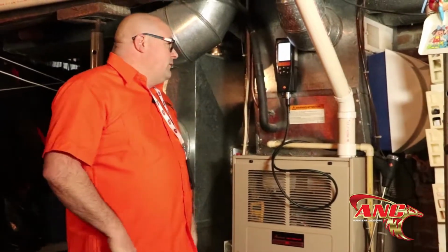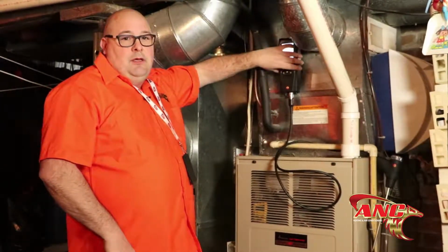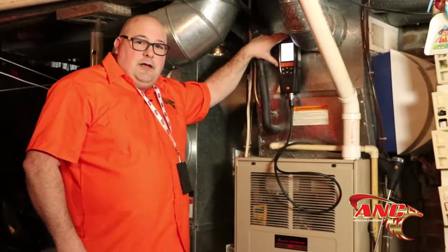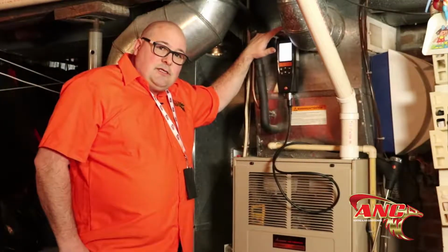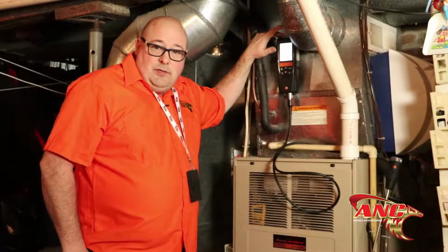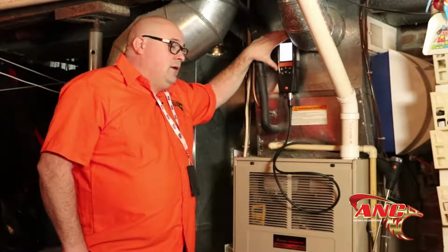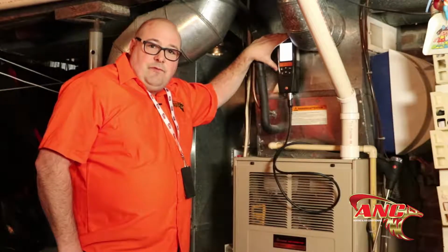So maintenance, very important, let's get them done. So what do we do on a maintenance? We're going to start with this device right here, it's called a combustion analyzer. If somebody's doing your maintenance and they're not using one, they aren't doing a maintenance, they are not checking the safety of your furnace.